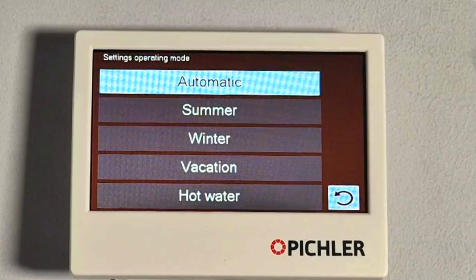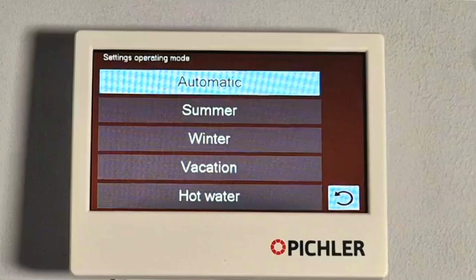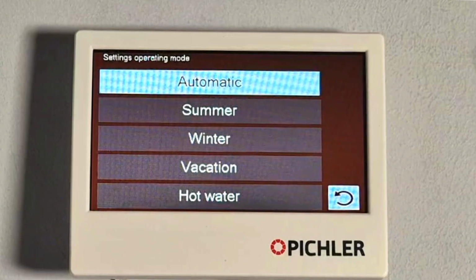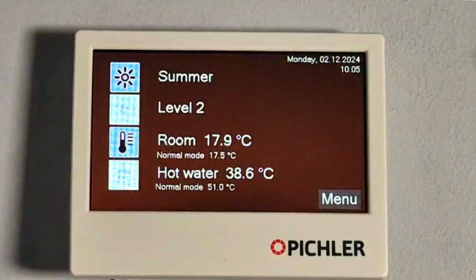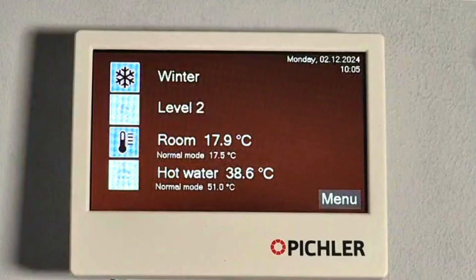The system can stay in automatic all year round as it decides what season it is in. It will be able to heat and cool depending upon the selected season. If we need to force the system into another mode, we can simply select it by pressing summer, which will mean the system will still ventilate and it will cool if required. If we put the system into winter, the system will only allow to heat, but it will constantly ventilate whilst doing so. And then the other modes we have are vacation and hot water.